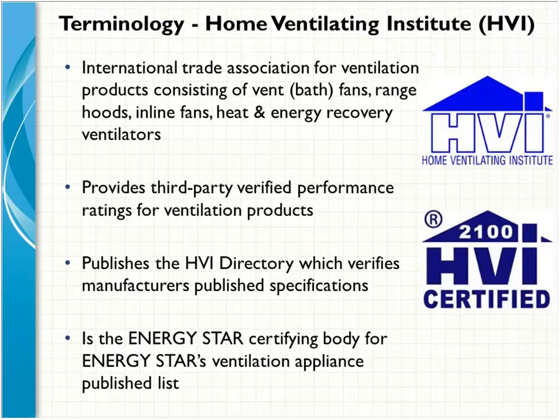Also, HVI is the organization that certifies a piece of ventilation equipment as Energy Star rated. So if it meets a certain efficacy with CFM per watt, it will be HVI that's doing that testing to give it its Energy Star certification. And they also test for sone levels, or noise.